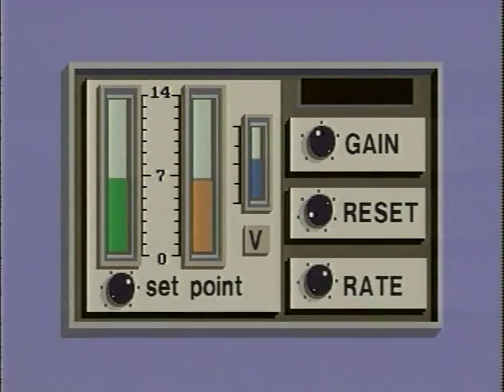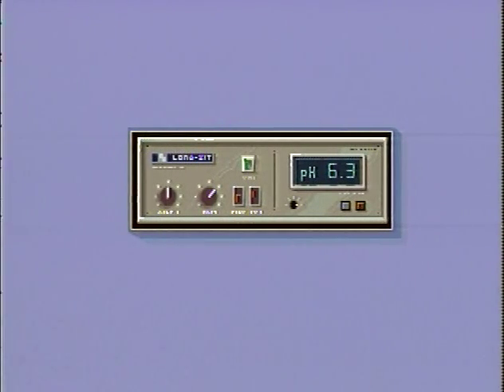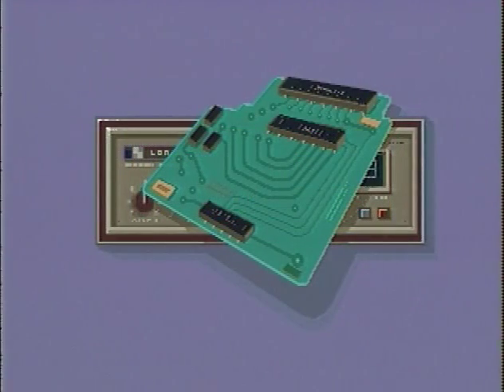Some years ago, this would have meant that a plant operator would have to continuously monitor the pH and then adjust the controller whenever the pH went over 6.4. But now, with the aid of microelectronics, it's possible to use controllers that will automatically adjust gain, reset, or rate to compensate for non-linearities. The controller contains a small computer, which is programmed to change the controller's response when an error is not corrected at the current setting. Because the controller adapts its response to a change in conditions, it is known as an adaptive control system. Adaptive control is typically used in situations where the process gain is non-linear, just like our example of a pH process.